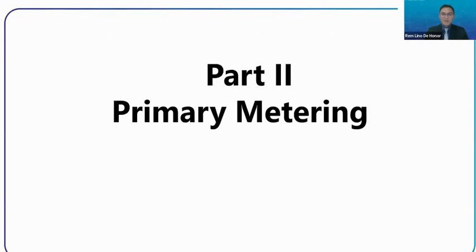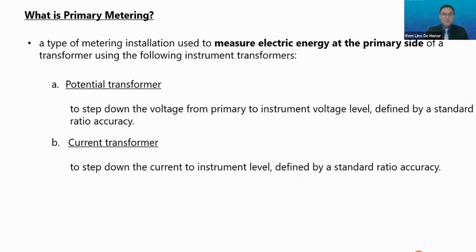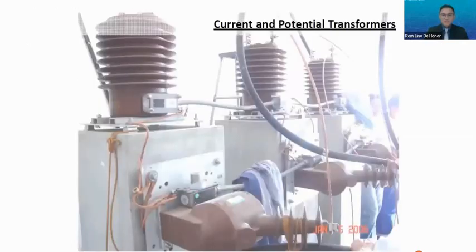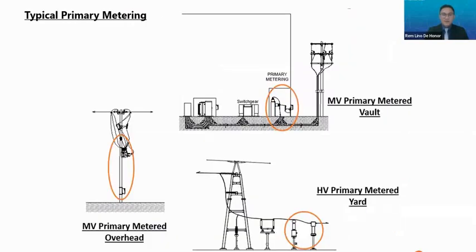Now, let's proceed to our second part, the primary metering. What is primary metering? A type of metering installation used to measure electric energy at the primary side of the transformer using the following instrument transformers: the PT and CT. PT, or potential transformer, is used to step down the voltage, and CT, or current transformer, is used to step down the current. Here are examples of a current and potential transformer. Also, the figure shows typical primary metering.